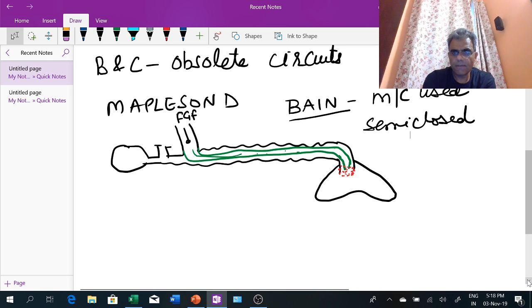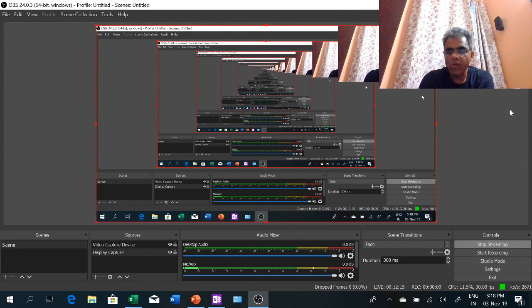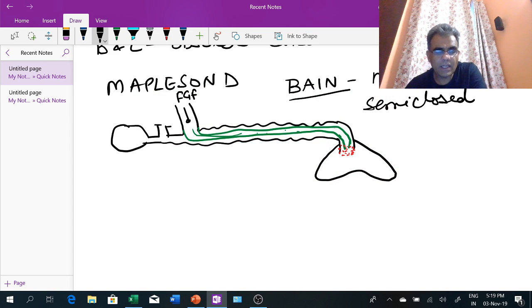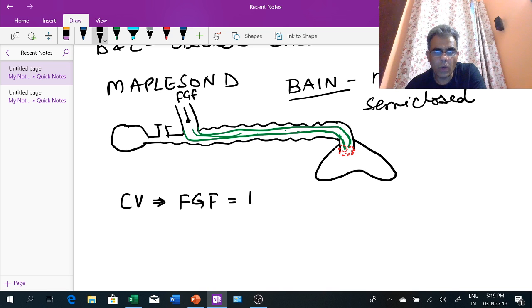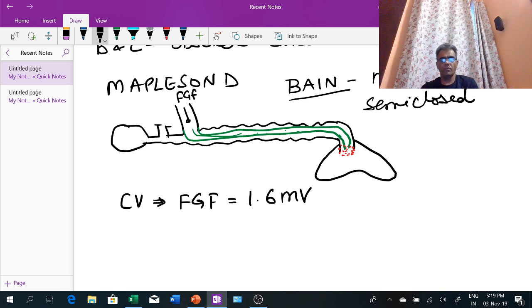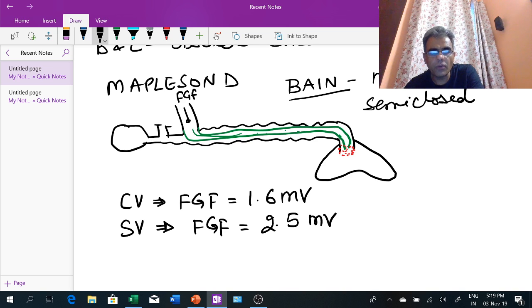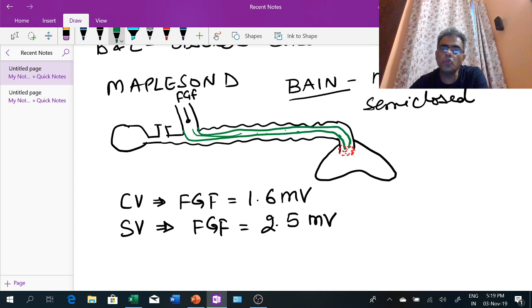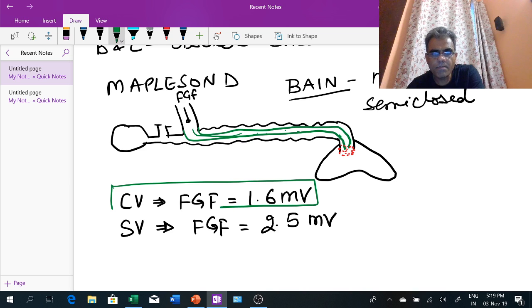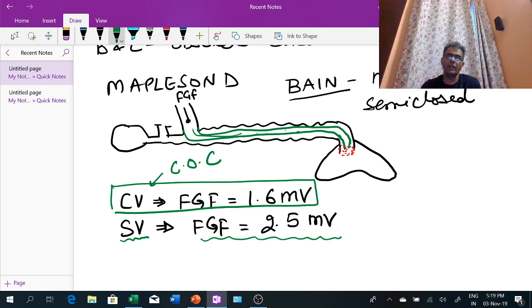Fresh gas flow recommendations for Bain's circuit: if used for controlled ventilation, fresh gas flow should be 1.6 times the minute volume. It can also be used for spontaneously breathing patients, but in that case fresh gas flow will be higher at 2.5 times the minute volume. Since Bain's consumes less gas for controlled ventilation, it is the circuit of choice for controlled ventilation.